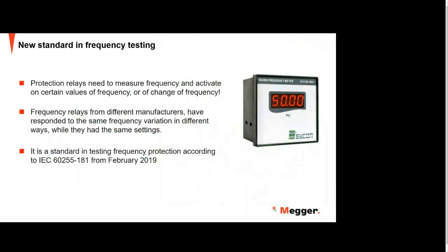So we have the new standard in testing frequency protection and about frequency relays. In the past, it had been like this. The frequency relays from different manufacturers responded to the same frequency variation in different ways while they had the same settings. This has been a problem, because testing one manufacturer with the same settings, you could have one result. Testing another manufacturer of relay, you can have another result. So actually it was very confusing. It is still very confusing to test frequency relays. But this new standard will help you to make everything equal in terms of relays, and also in terms of how to simulate a frequency change from the relay test set.